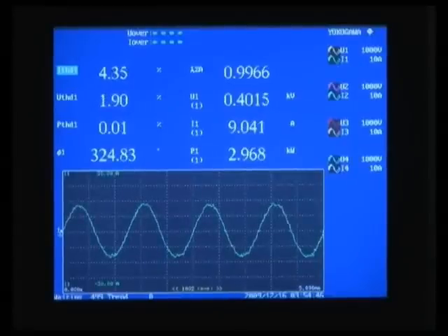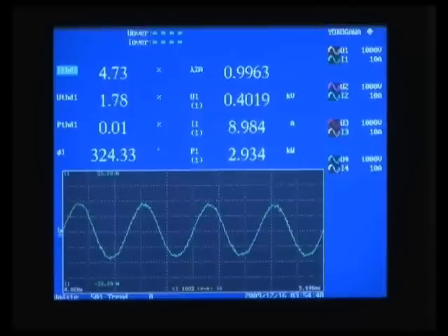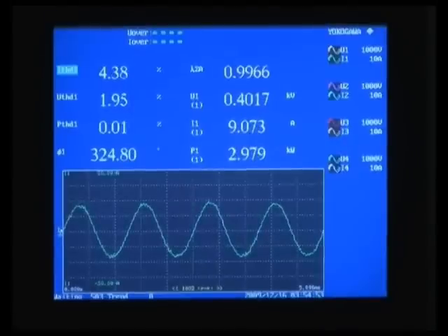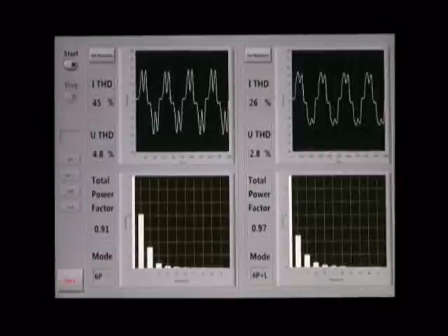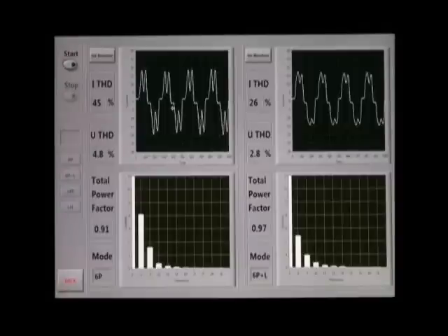At this point, let's capture a few of these waveforms and examine them side by side using the computer screen. When we had individual displays of these waveforms on the harmonic analyzer, while we could see the level of harmonics, we didn't have the side-by-side comparison that we have now. It's very easy to note from this side-by-side comparison the dramatic improvement that simply adding an inductor to a 6-pulse drive can add to the waveform.